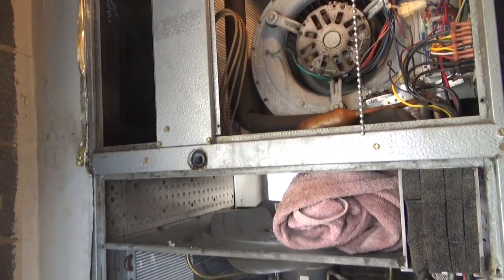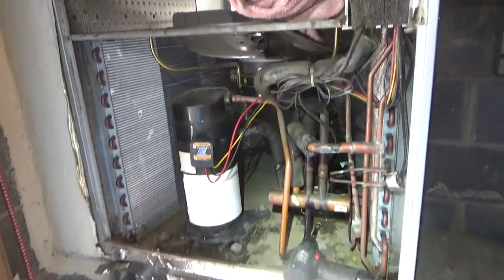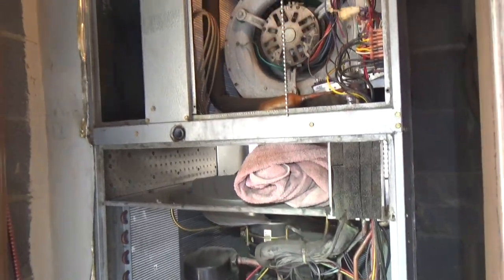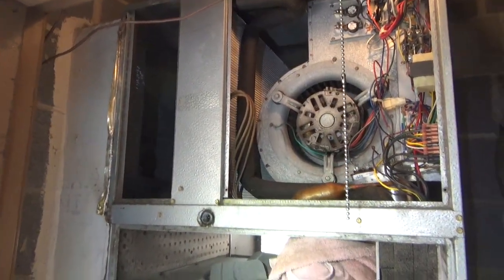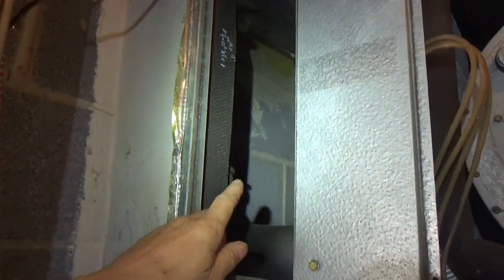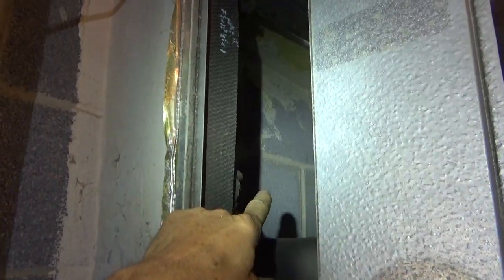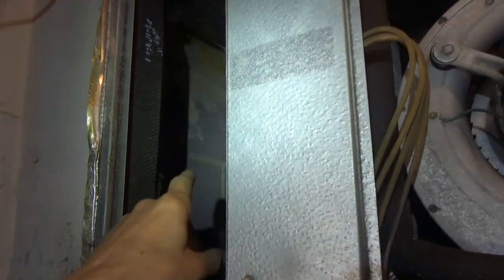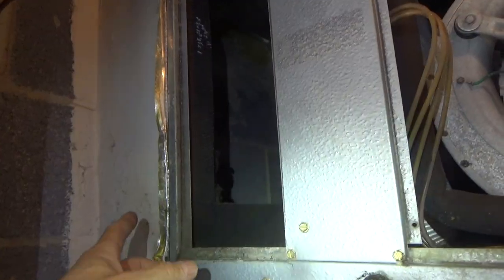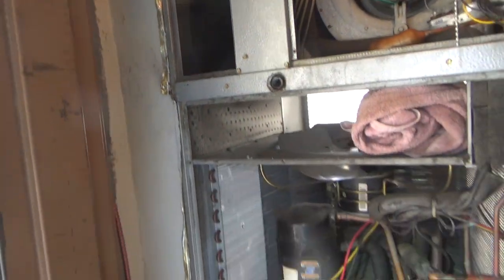So in this job, I'm going to show start to finish upsizing from a 2-ton to a 2.5 ton for the top floor, and then how to do the ductwork on the side. And I'm also going to insulate it, because notice the brick there, they would have been losing quite a bit of heat through the brick wall with the air rushing against it.